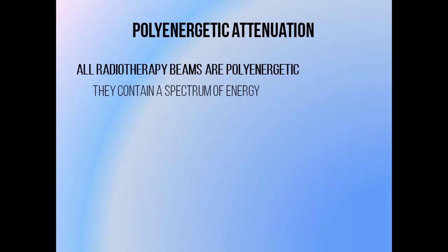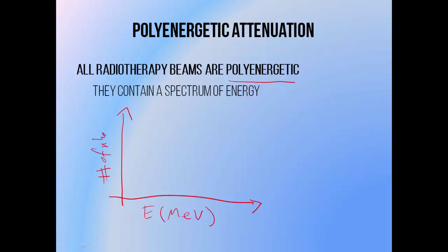Radiotherapy beams are polyenergetic — made up of a whole spectrum of different energies. If the x-axis is photon energy in MeV and the y-axis is the number of photons at each energy, the beam's energy spectrum will generally have a maximum energy. For example, a 6 MV beam (labelled by its maximum energy) is mostly composed of photons with a much lower energy, but contains fewer very low-energy photons because we filter those out in clinical practice. If the beam wasn't filtered, the number of photons would continue to increase as energy decreases.